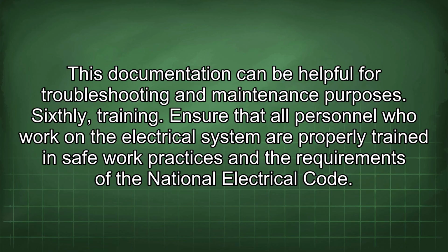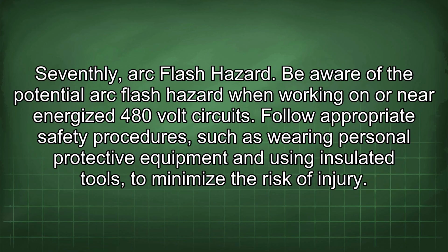Sixthly, training. Ensure that all personnel who work on the electrical system are properly trained in safe work practices and the requirements of the National Electrical Code. Seventhly, arc flash hazard. Be aware of the potential arc flash hazard when working on or near energized 480-volt circuits. Follow appropriate safety procedures such as wearing personal protective equipment and using insulated tools to minimize the risk of injury.